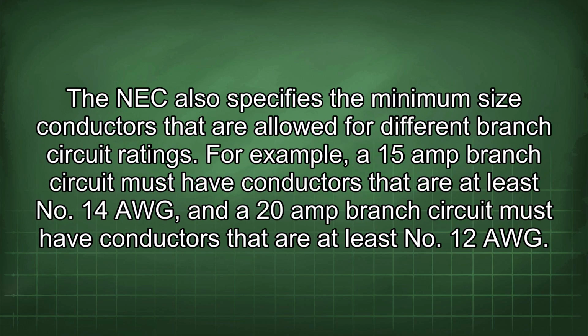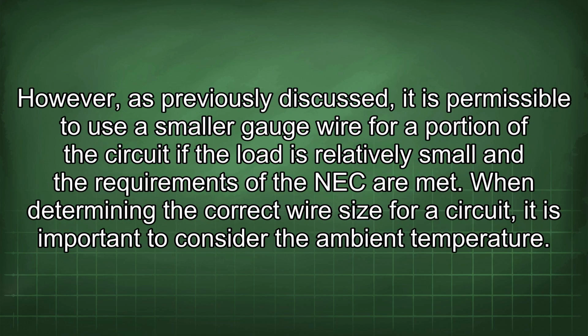The NEC also specifies the minimum size conductors that are allowed for different branch circuit ratings. For example, a 15 amp branch circuit must have conductors that are at least 14 AWG, and a 20 amp branch circuit must have conductors that are at least 12 AWG. However, as previously discussed, it is permissible to use a smaller gauge wire for a portion of the circuit if the load is relatively small and the requirements of the NEC are met.